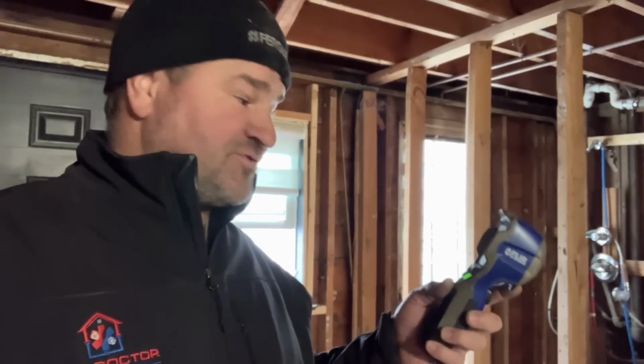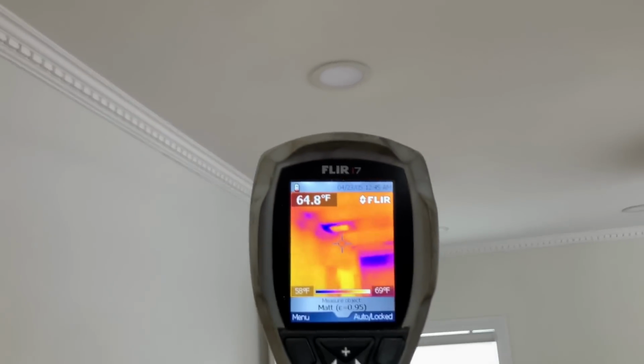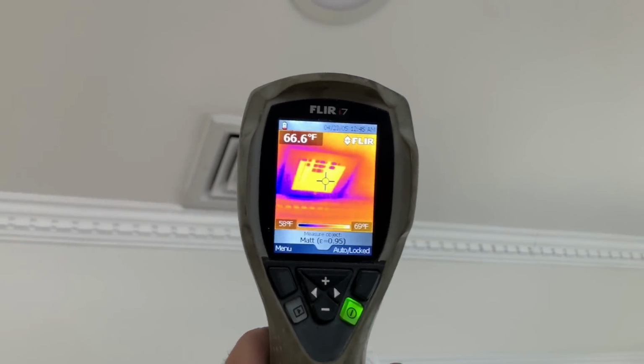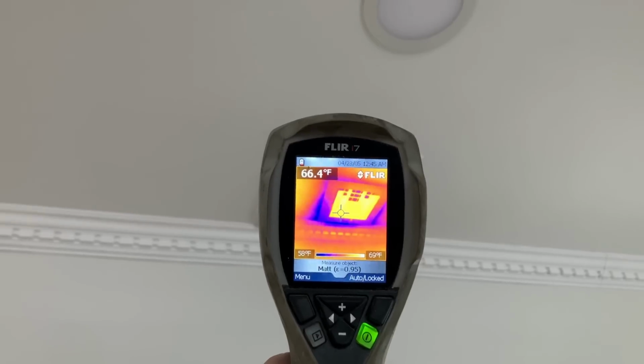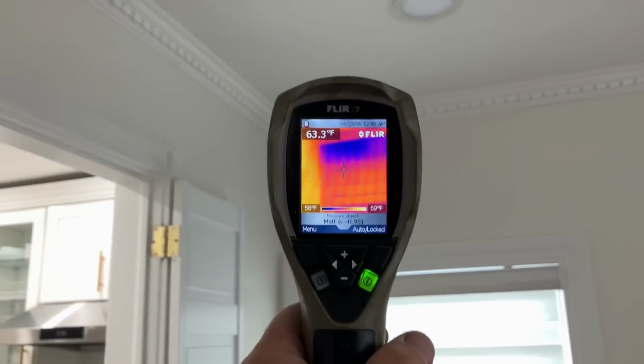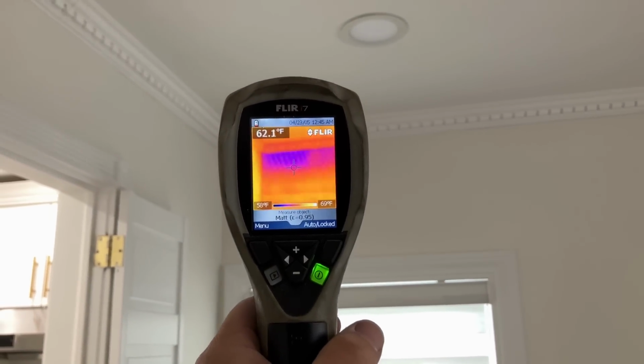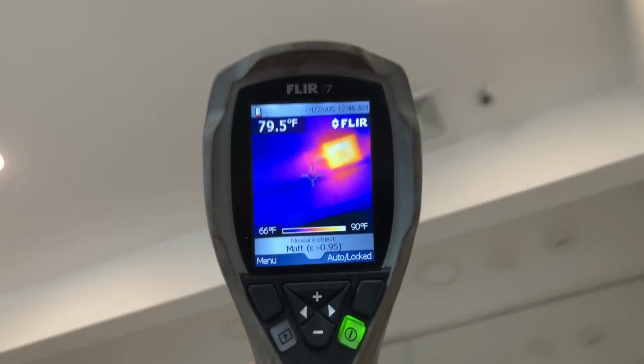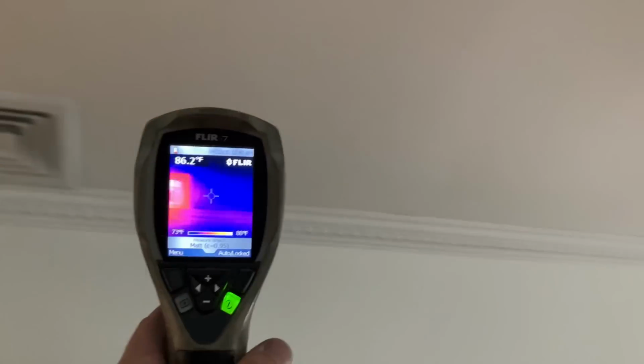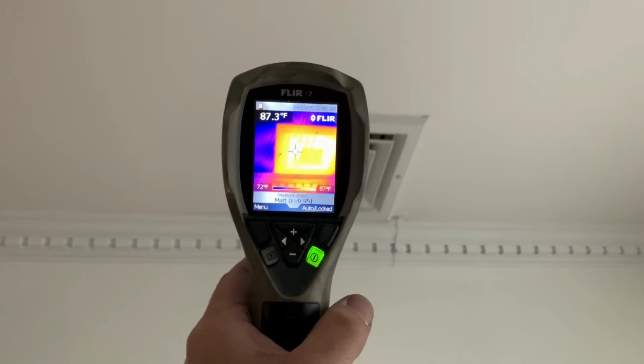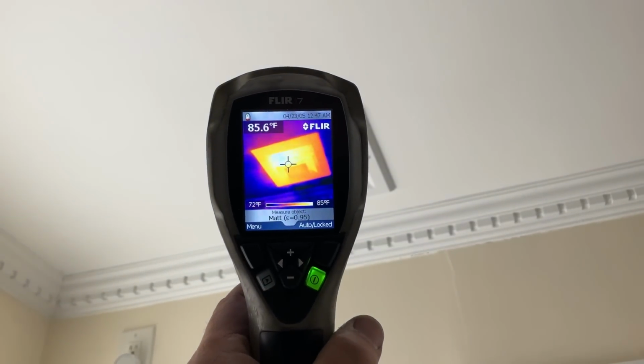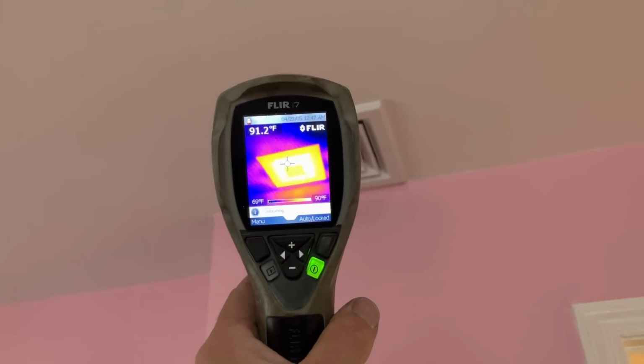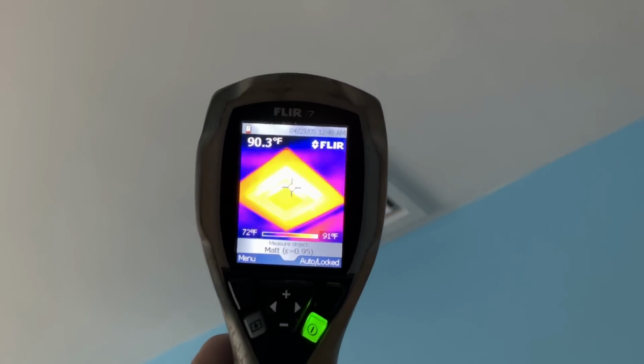All right, I'm gonna now use a thermal imaging camera. We're gonna make sure that we have heat coming out of the vents it's supposed to, and properly finish commissioning and start up of the system. And we're out of here. What's great about thermal imaging cameras is that you can also see efficiency loss. Look at the cold air around the center of this diffuser. And then above the corner of this window. Ooh, that may be some water damage actually. Beautiful, beautiful. All right, ooh, nice and toasty up here. 90 degrees discharge temperature. Another one close to 90, beautiful. Here's one in the master bathroom. Beautiful. Kids' bedroom, nice. Another kid's bedroom, also very nice.